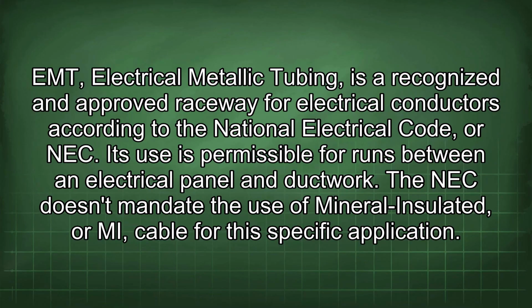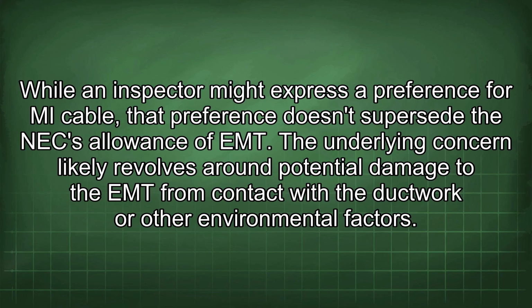EMT, electrical metallic tubing, is a recognized and approved raceway for electrical conductors according to the National Electrical Code, or NEC. Its use is permissible for runs between an electrical panel and ductwork. The NEC doesn't mandate the use of mineral insulated, or MI, cable for the specific application. While an inspector might express a preference for MI cable, that preference doesn't supersede the NEC allowance of EMT.